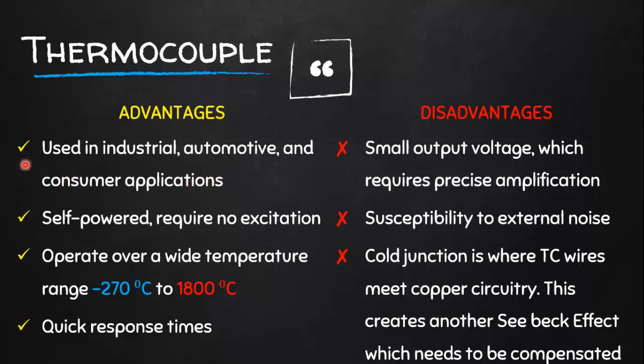The main advantages of thermocouples are that they are widely and commonly used in industrial, automotive, and consumer applications. They are self-powered and require no excitation. They can be used for a wide temperature range from minus 270°C to 1800°C, and they have a very quick response time.